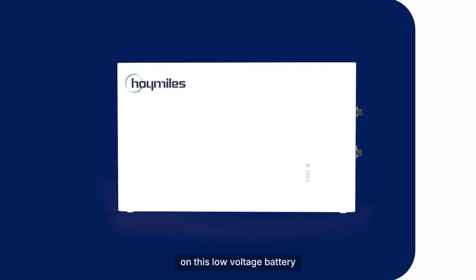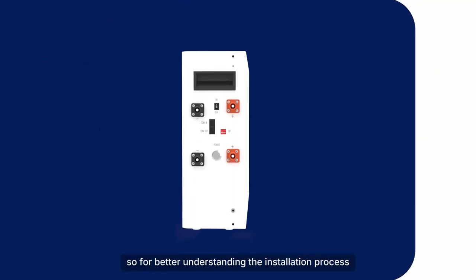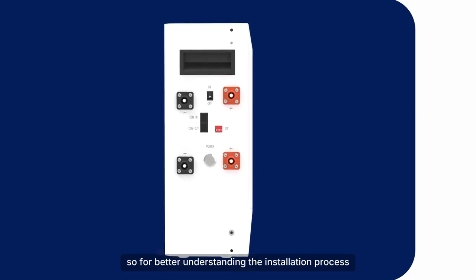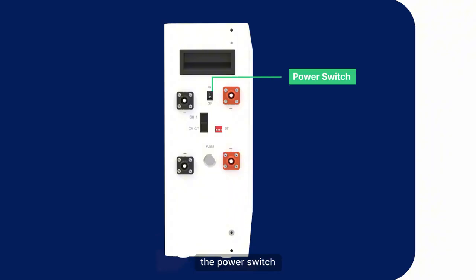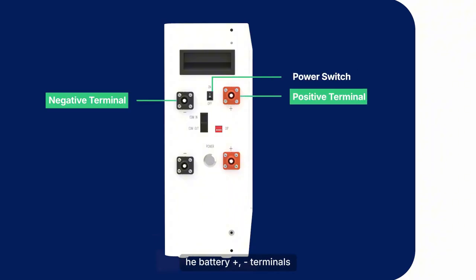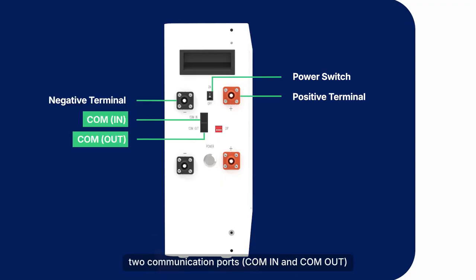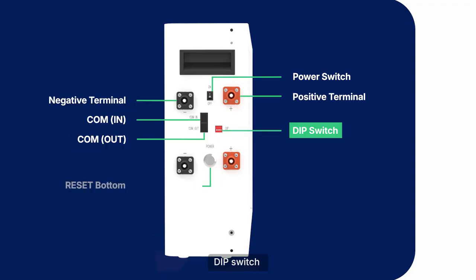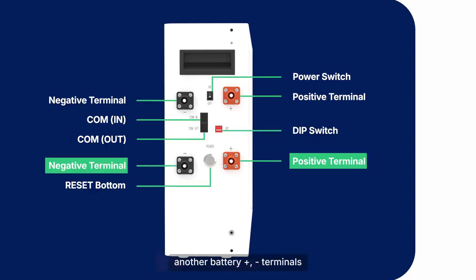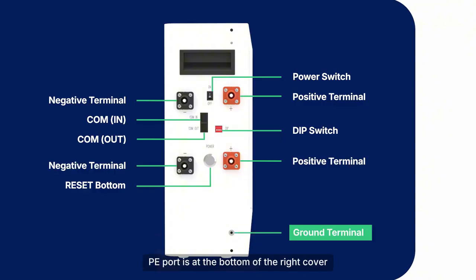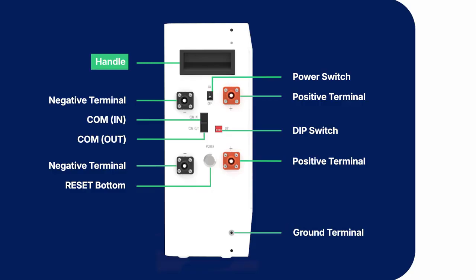Before we start, let's take a look at the ports on this low-voltage battery, for better understanding of the installation process. The wiring port of the battery right cover, from the top to the bottom: the power switch, the battery positive and negative terminals, 2 communication ports, dip switch, reset button, another battery positive and negative terminals. PE port is at the bottom of the right cover. Both the left and right cover have one handle.